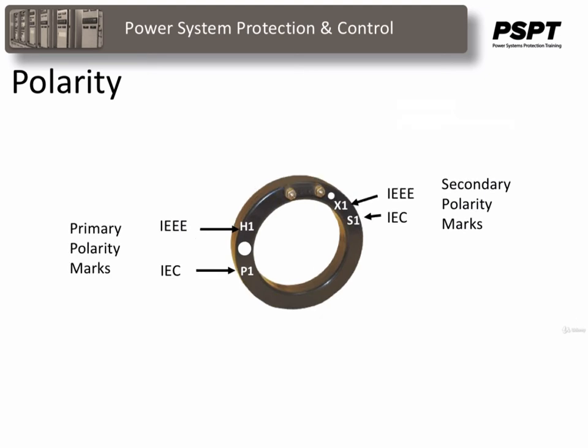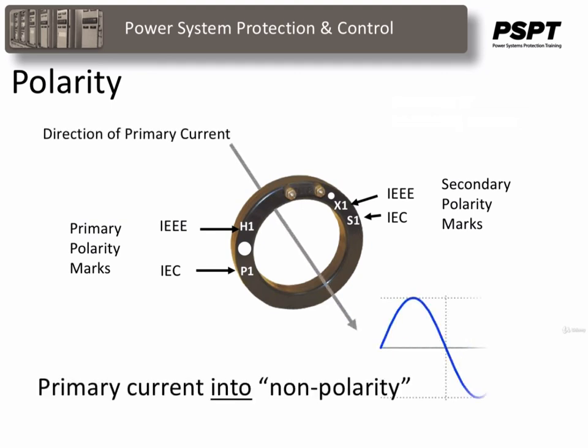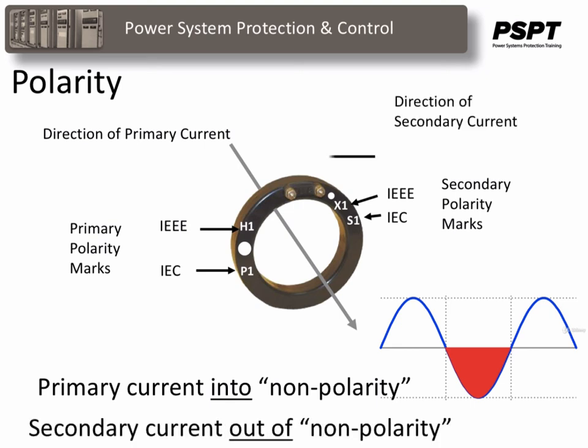And what this also indicates is that when the primary current is negative during the sinusoidal half cycle, or the current is out of the polarity spot on the primary, the secondary current will be out of the non-polarity spot of the secondary. So the primary current is negative during the sinusoidal half cycle, current out of the polarity spot. The secondary current will be out of the non-polarity spot. This is sometimes shortened to primary current flowing into a spot results in secondary current flowing out of the spot.